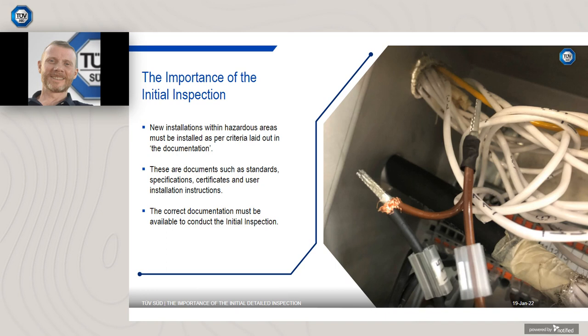New installations within hazardous areas must be installed as per criteria laid out in the documentation. These documents include standards, specifications, certificates, and user installation instructions. Descriptive system documents, hazardous area drawings, loop drawings, detailed installation drawings, user instructions, and certificates are all such documents. The correct documentation must be available to conduct the initial inspection.